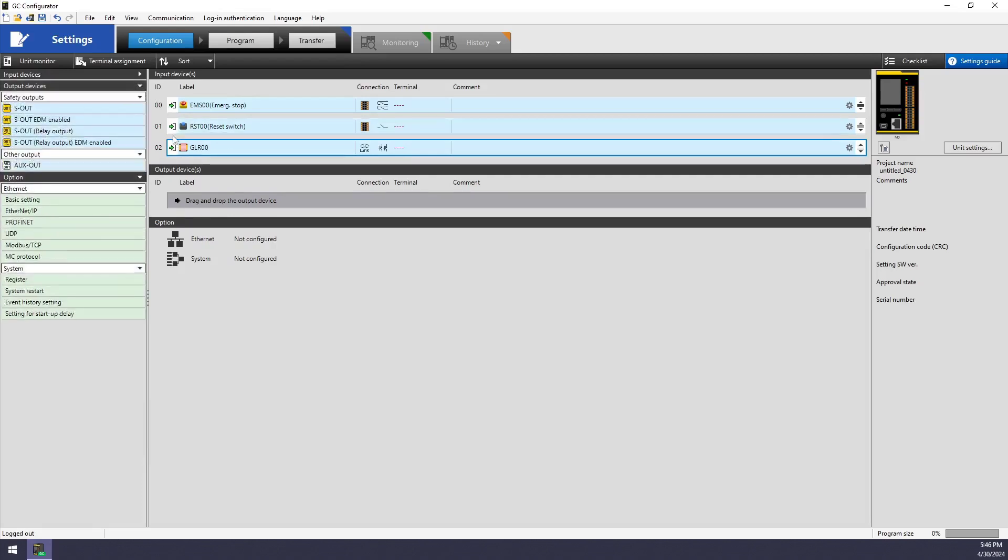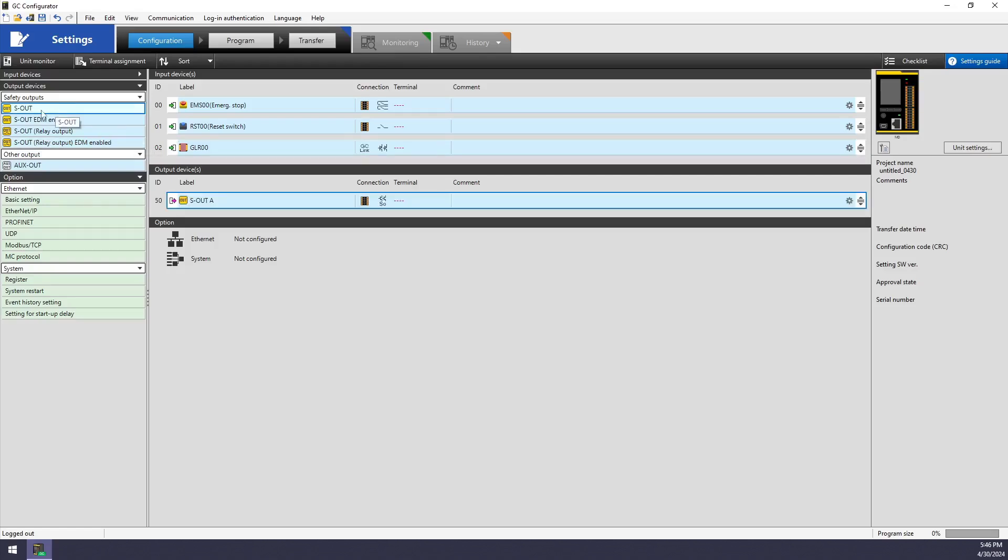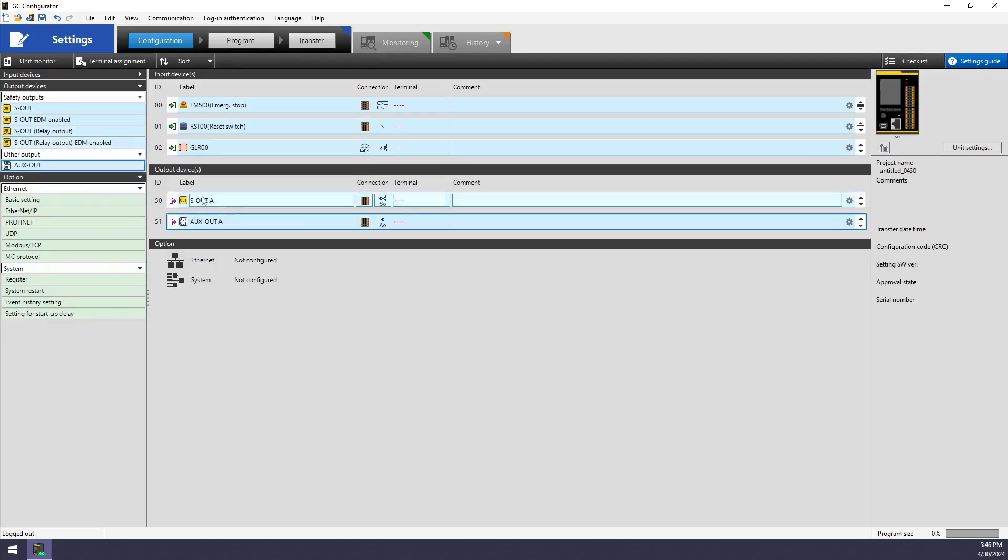And now I need to add my output devices, which can send control outputs or status outputs. I'll be using a set of the safety output terminals to control an external relay. And I'll also be using an auxiliary output, which will turn on an indicator whenever I'm waiting on my e-stop to be reset with the push button.